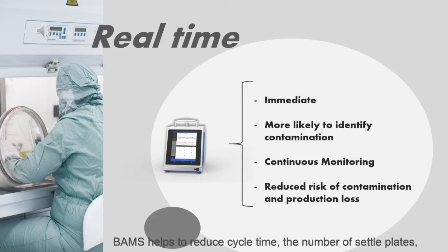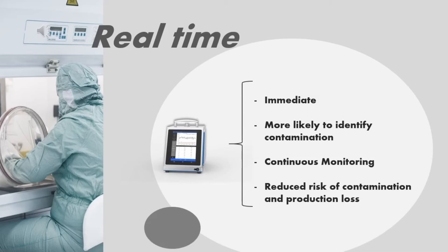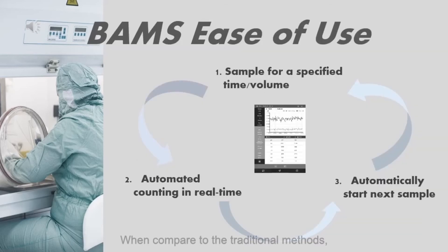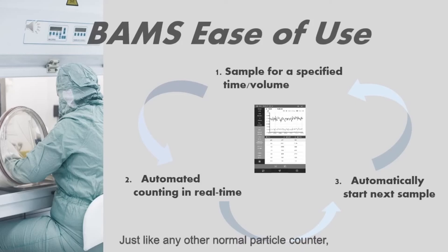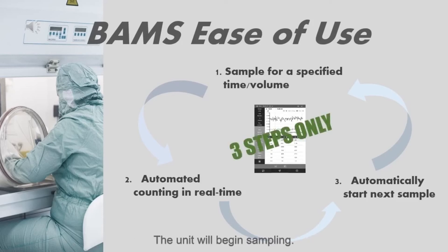BAMS helps to reduce cycle time, the number of settle plates, grab samples, cleaning time, related labor cost, and storage cost by expediting final product release using real-time results. When compared to traditional methods, BAMS is much easier to use. Just like any normal particle counter, users set a specified time or volume for sampling. The unit will begin sampling, then counts are displayed on screen in real time.